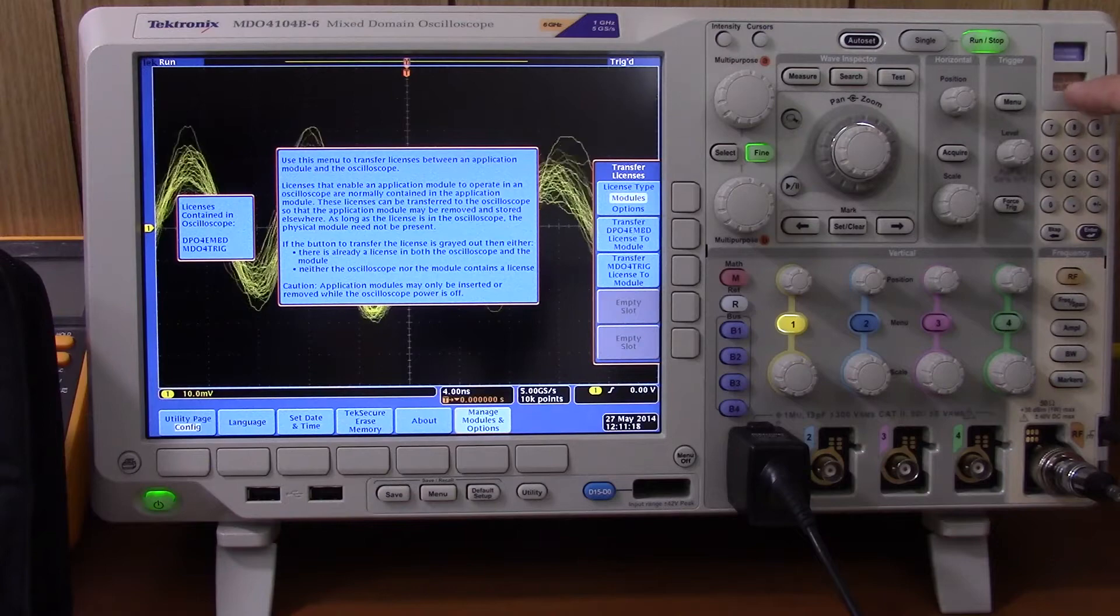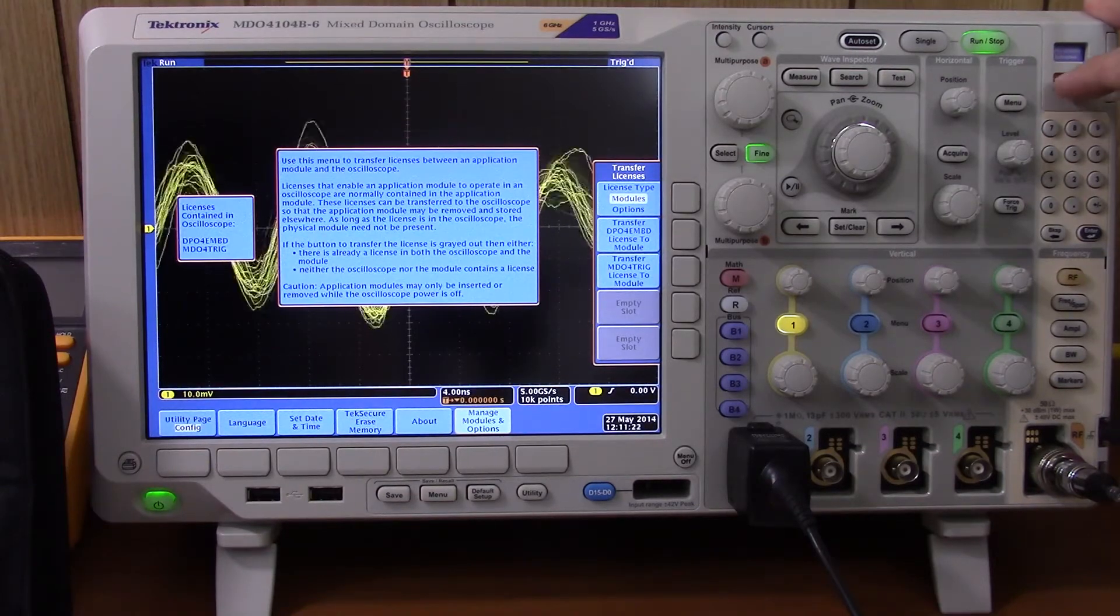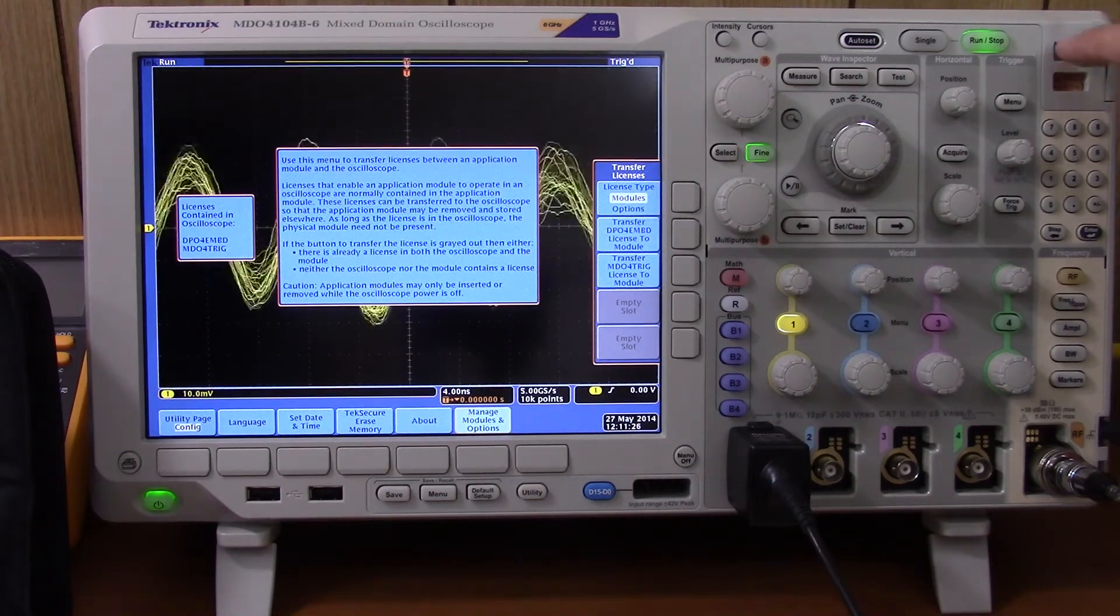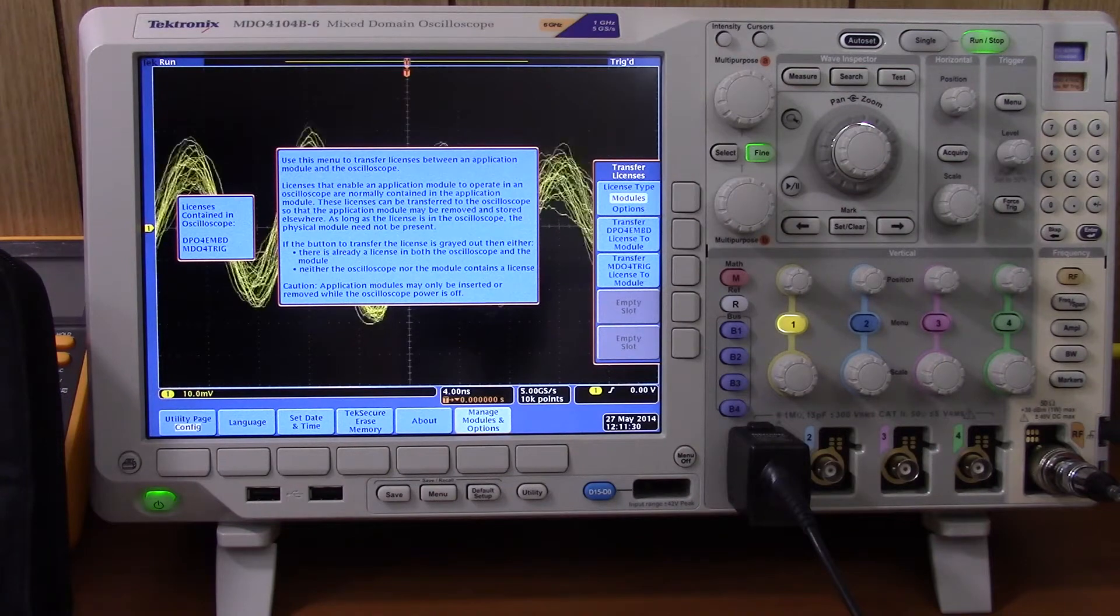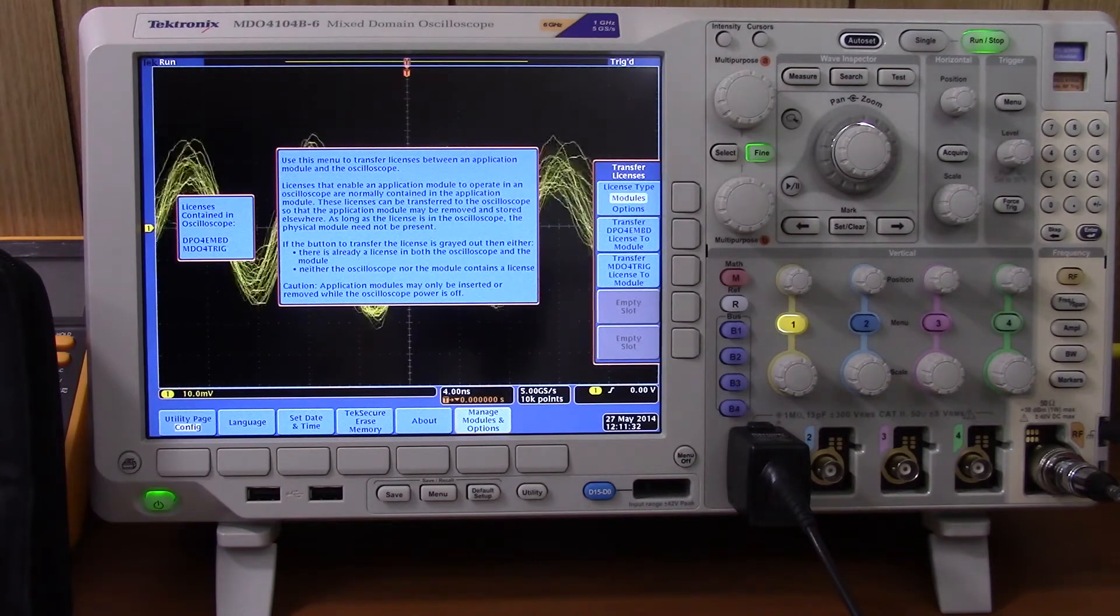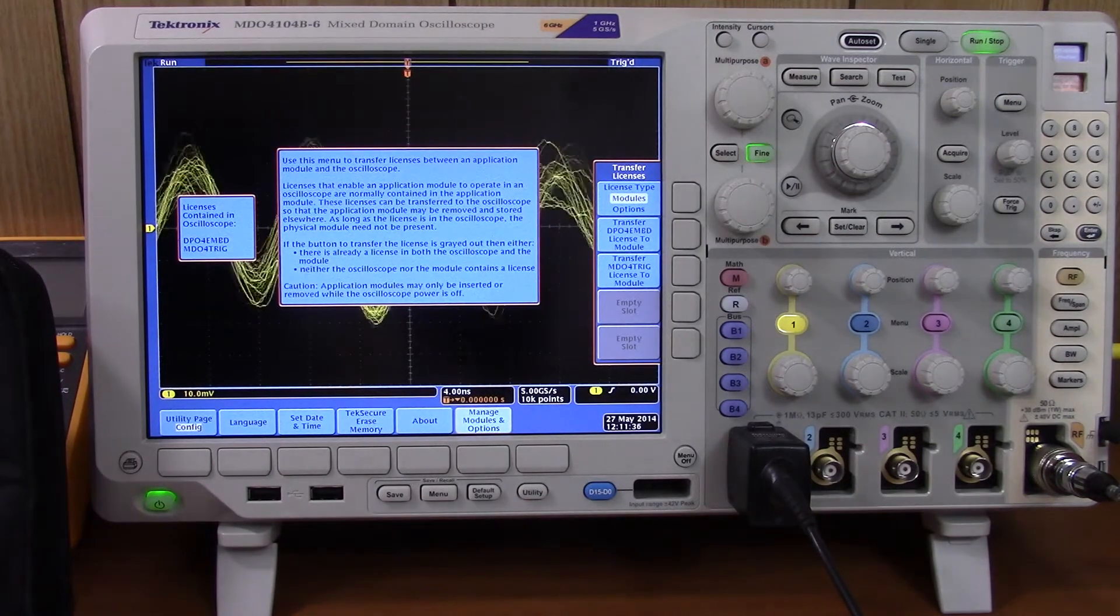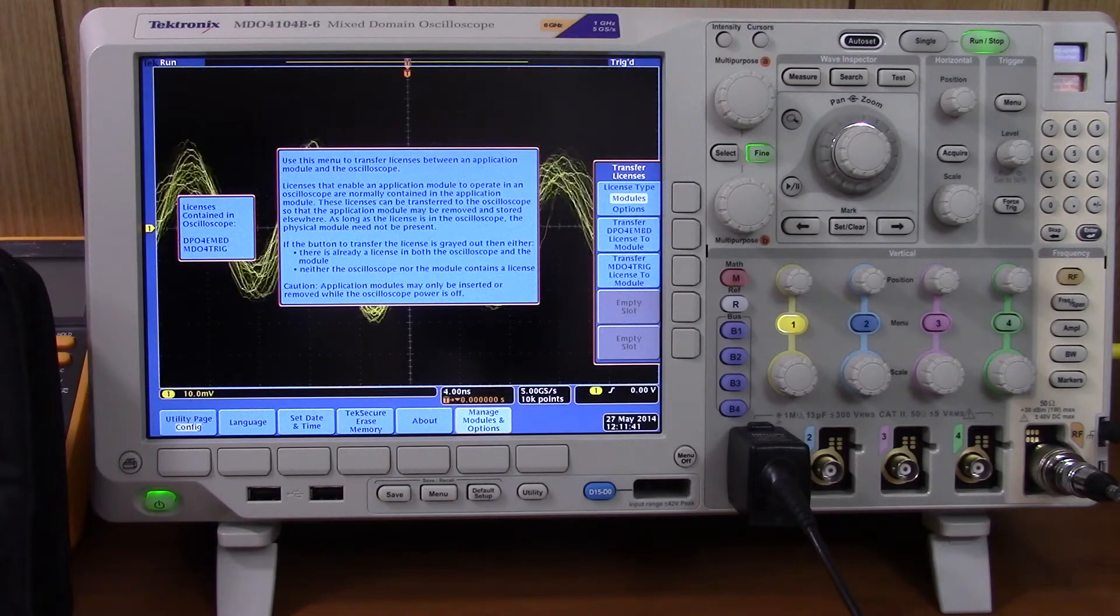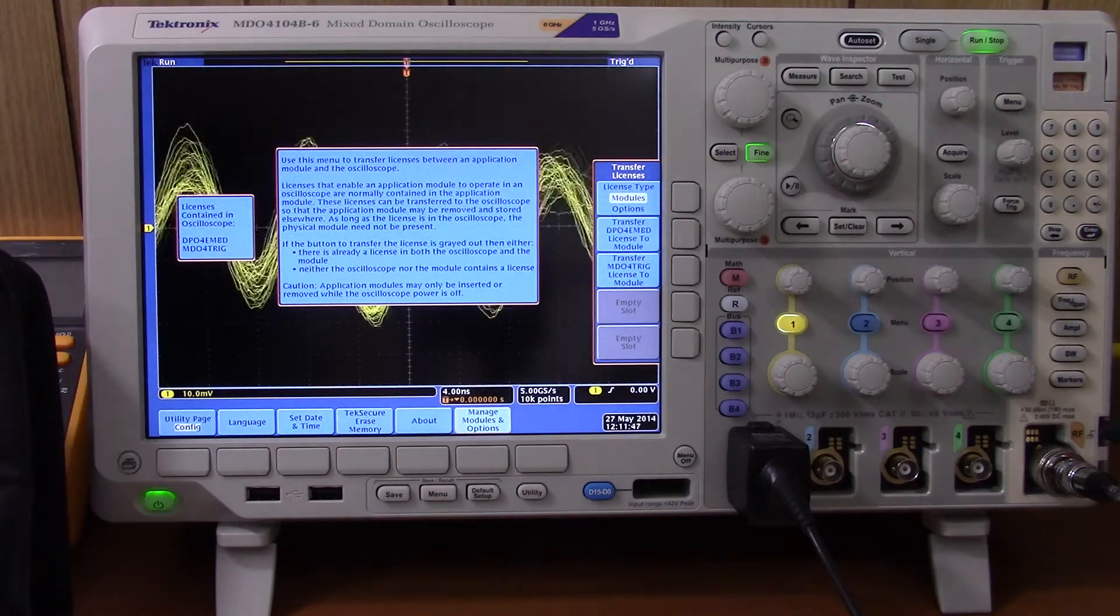The license now actually lies on the oscilloscope. Now you can take these two modules out, of course, after shutting down the oscilloscope, put them in a drawer, put them in a safe place somewhere where they don't get lost. But they are essentially worthless as for activating any options on an oscilloscope. They basically, if you think about it, you can think of them as a carrier media, kind of like a USB stick to carry the licensing file.